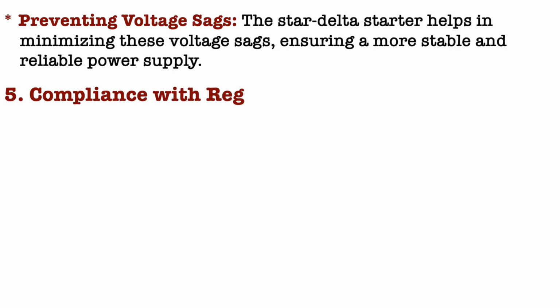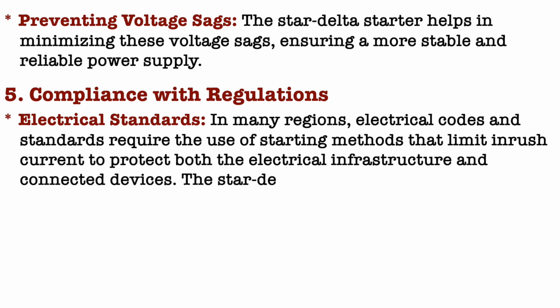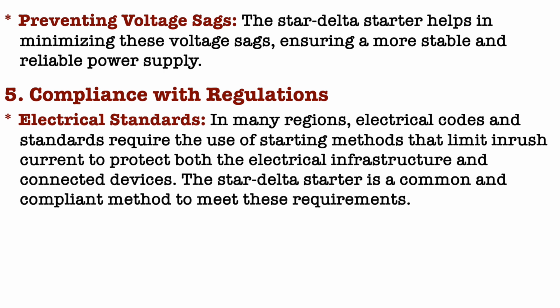Next reason is compliance with regulations. In many regions, electrical codes and standards require the use of starting methods that limit inrush current to protect both the electrical infrastructure and connected devices. The star delta starter is a common and compliant method to meet these requirements.